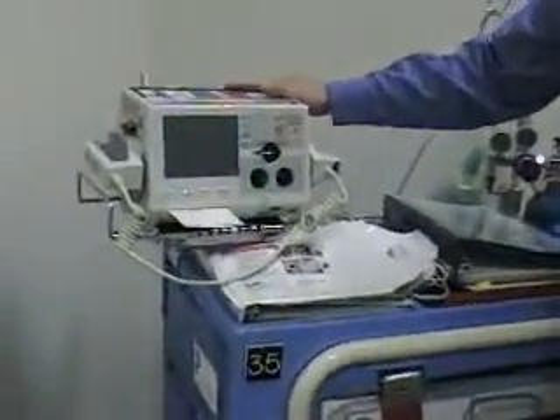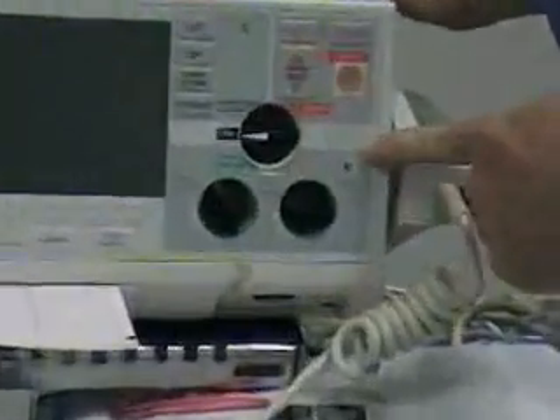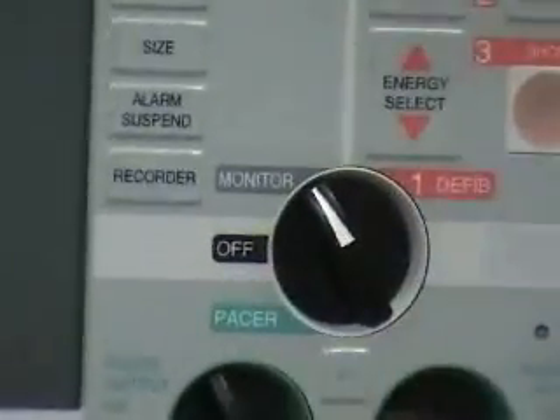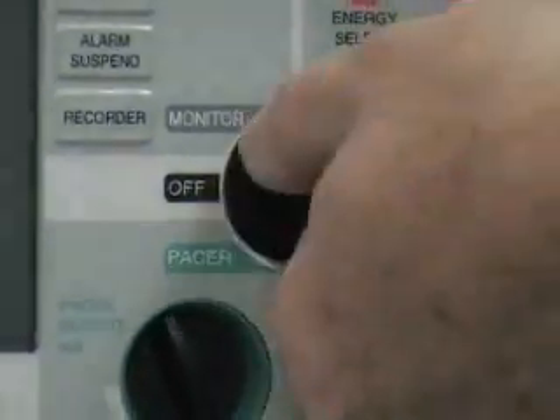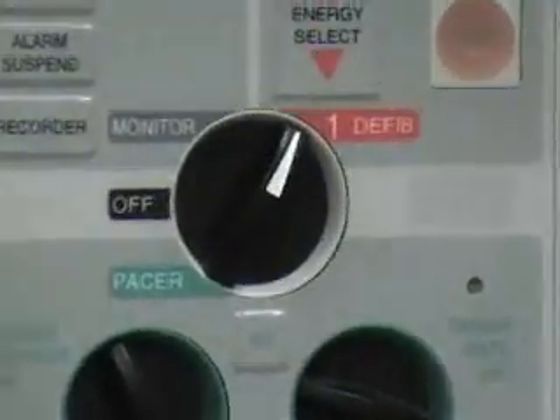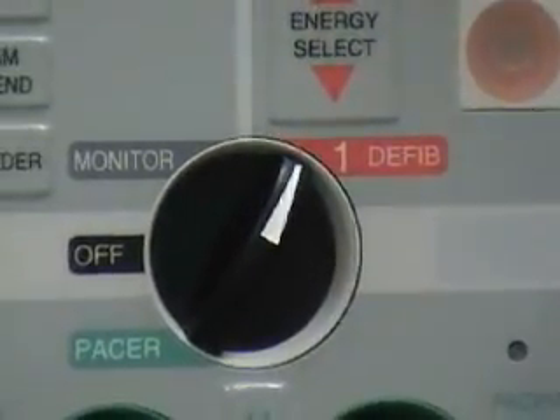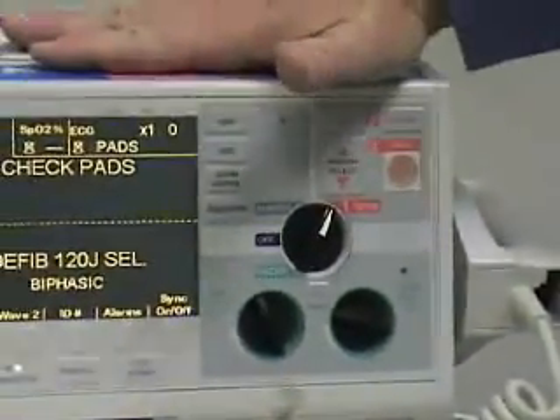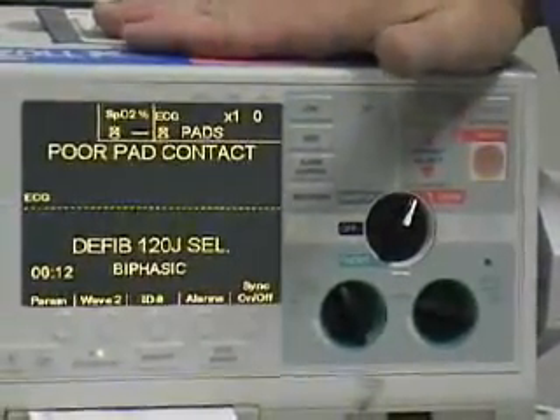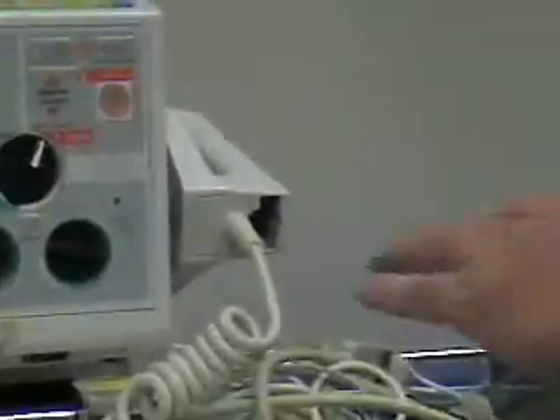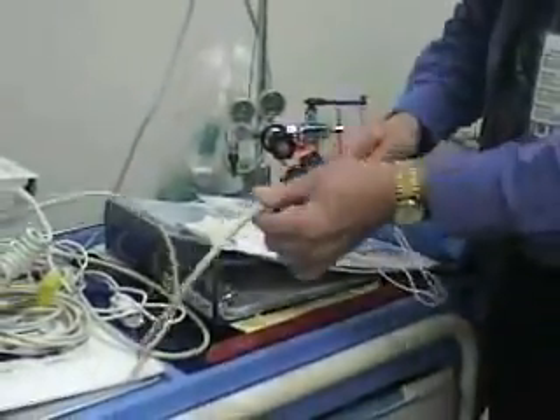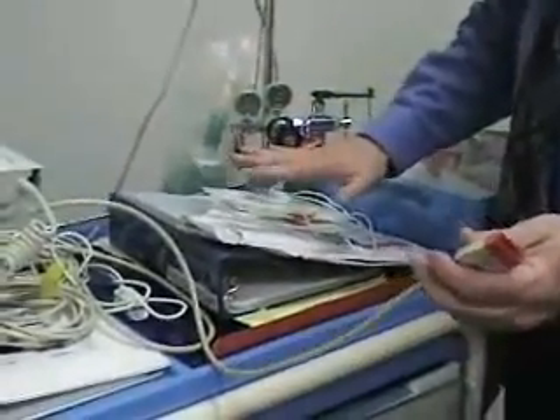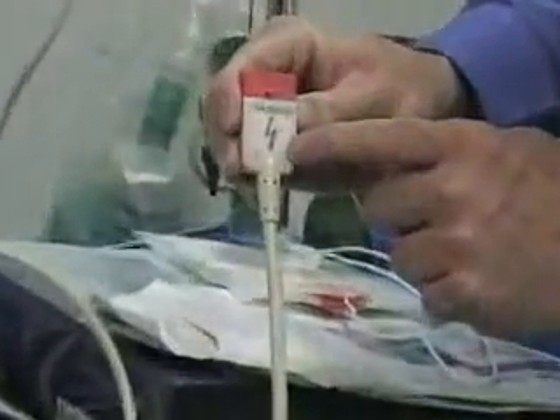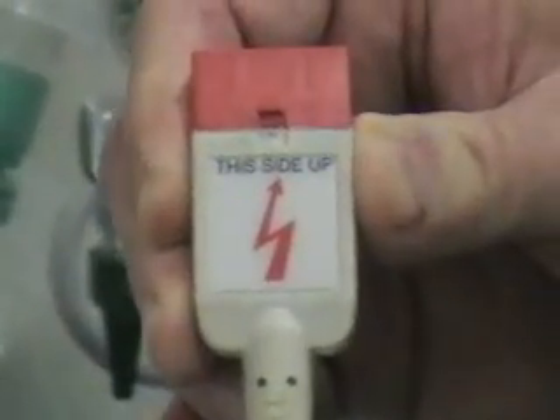So, we're going to test the defibrillator itself. One issue that people seem to have sometimes is they turn it on and they leave it at monitor. We're not testing the monitor, we want to test the defibrillator, so actually turn it all the way over to 1. You'll hear beeps, and you may even hear a voice prompt of some kind. However, just ignore that at the moment. What you're going to do is take the multifunction cable, disconnect it from the pads that may already be sitting in wait for patient use, disconnect that. You'll notice that there is a zigzag arrow on here that kind of refers to electricity.